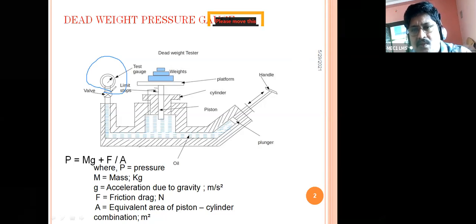The test gauge is not there yet. See here, it consists of weights placed on a platform, and a piston inside a cylinder, with a handle and plunger, and oil or some liquid inside. When the weights are placed on the platform, the piston drops down, thereby creating pressure in the oil.